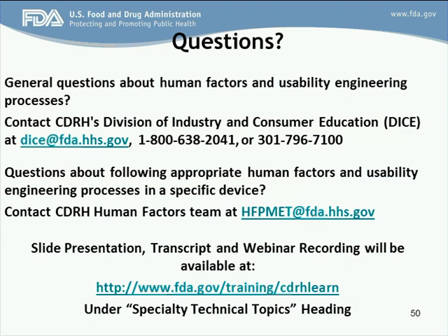Hi. I have two questions. Somewhat related to the comment that was just made, because this wasn't addressed in the guidance, but two things. One is, if you're going for over-the-counter labeling, we've got some feedback from the agency that our usability testing would have to incorporate the ability for the participants to self-select out of the testing, which is really independent of the errors and the use errors that you could run into. And so I wanted your feedback on that.